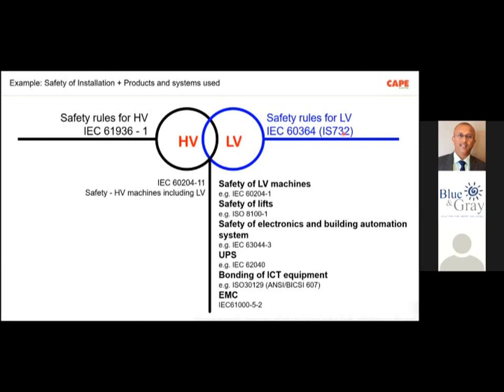So basically, in a low voltage electrical installation, the fixed part of the electrical installation, I would say the distribution boards, the wiring, the sockets, must be tested as per IS 732, and all the connected devices, such as, for example, low voltage machines. If you have an industry and if you buy a machine, once you install that machine, you must do the testing as per IEC 60204. The second one, lifts and elevators. Of course, in most modern buildings, you have lifts and elevators, and you must do the testing as per ISO 8100 Part 1. There is an Indian standard already in the making. Probably very soon that standard will come out.